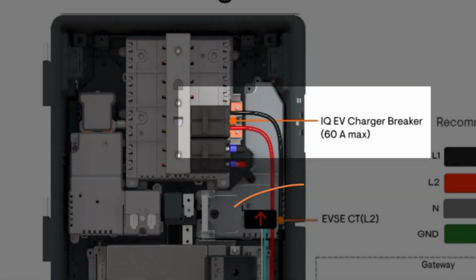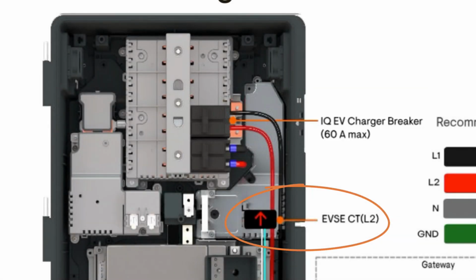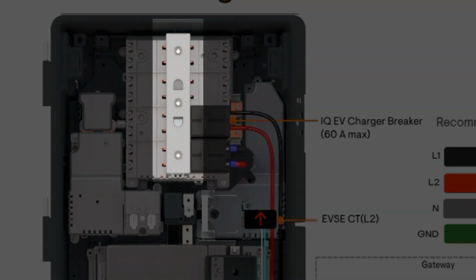Note: when installing an electric vehicle charger, an external CT will be necessary to monitor charger power flow. A standard in-phase split core or clamp-on CT will be wired onto the Line 2 conductor and connected on the gateway. In the center of the circuit breaker section is a circuit breaker hold-down bar to secure backfed breakers.